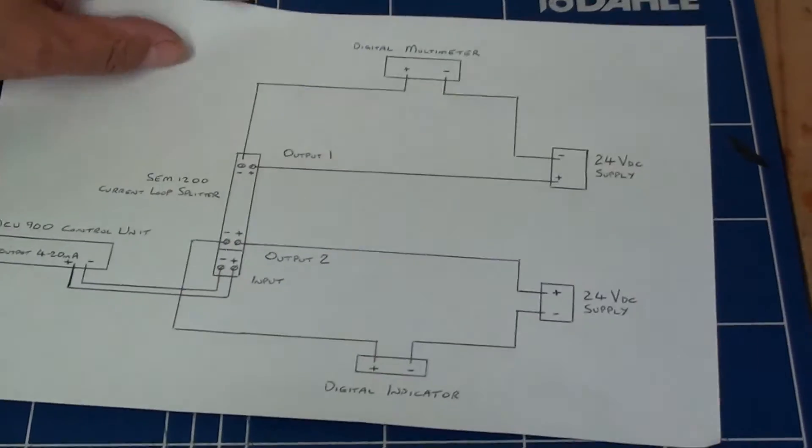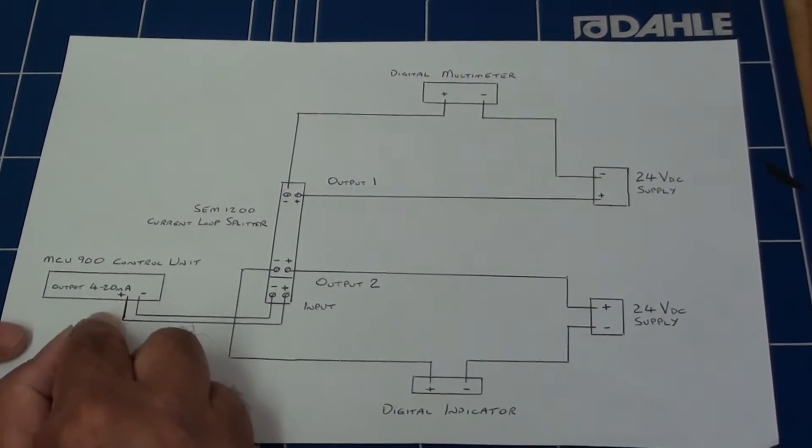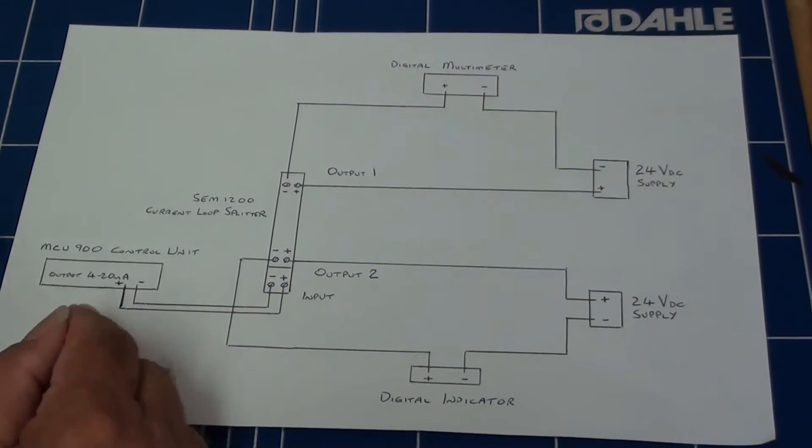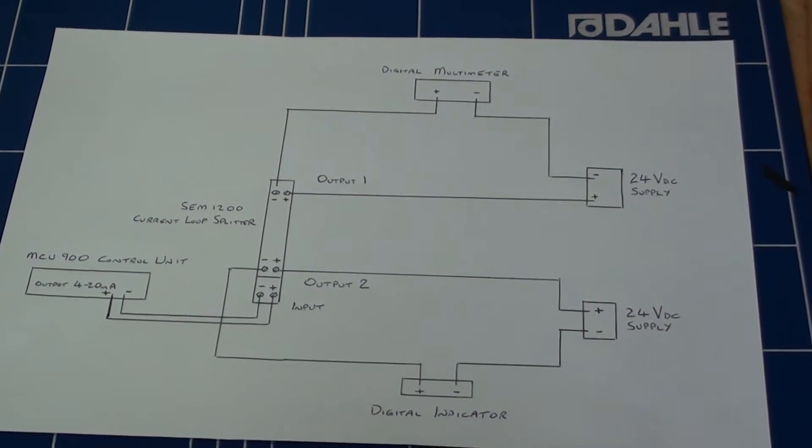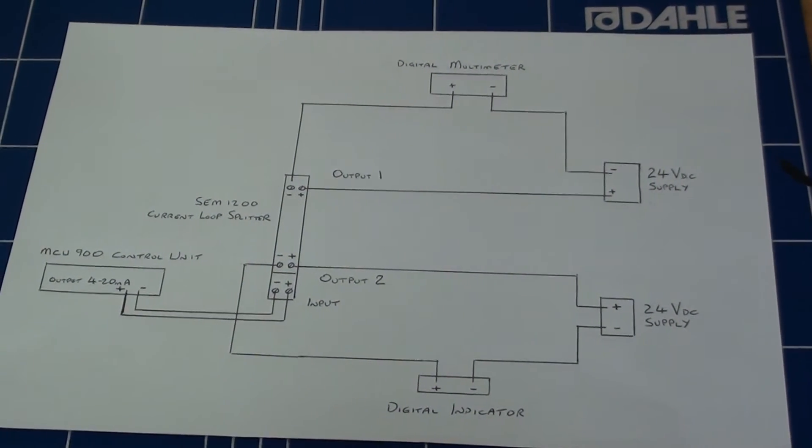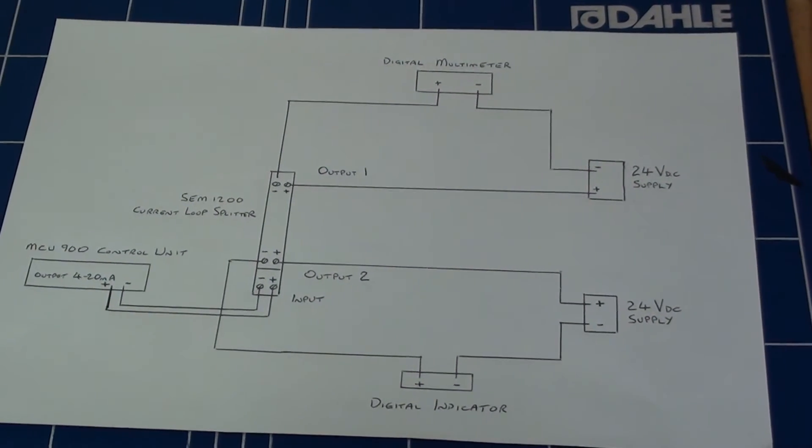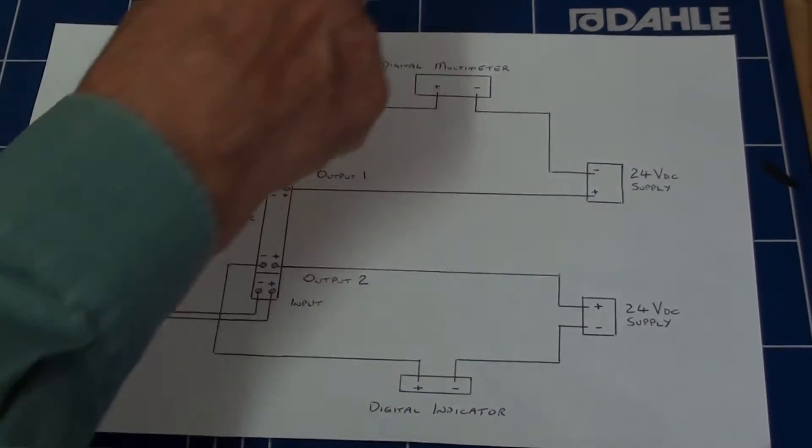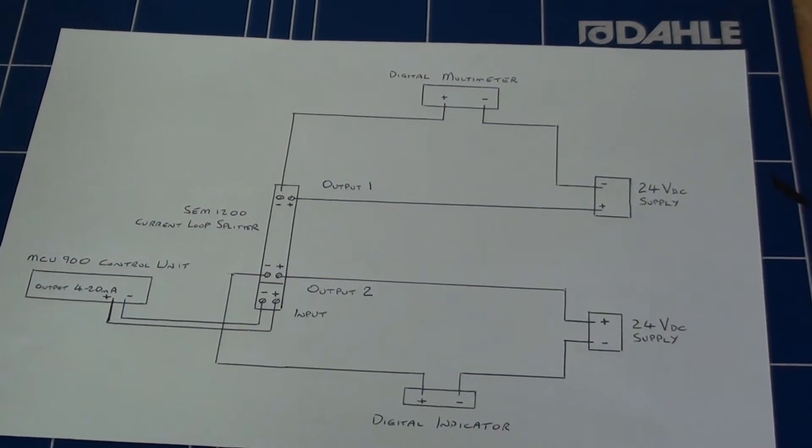If I now connect in the input signal from my simulated control unit here, the positive from the control unit goes to the positive on the loop splitter, and the negative from the control unit to the negative on the loop splitter. The terminals are down at the bottom.